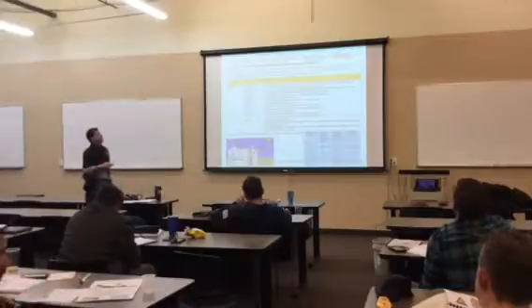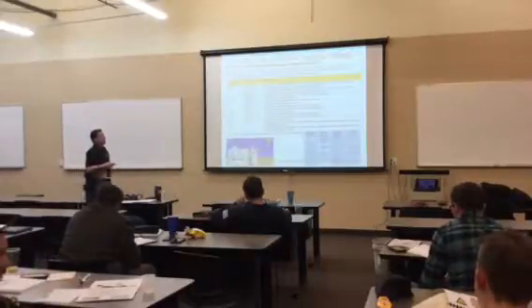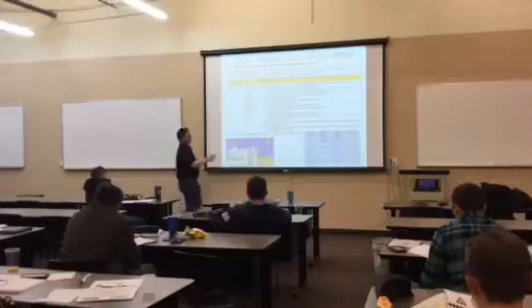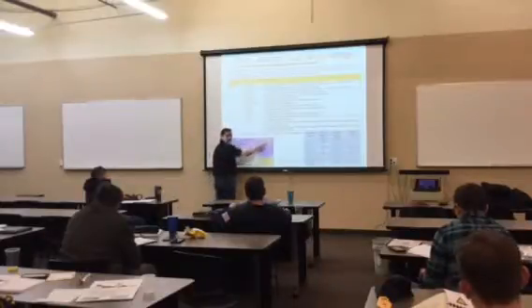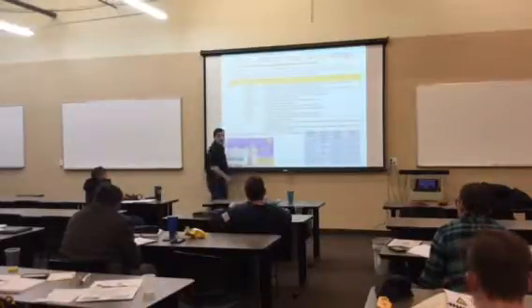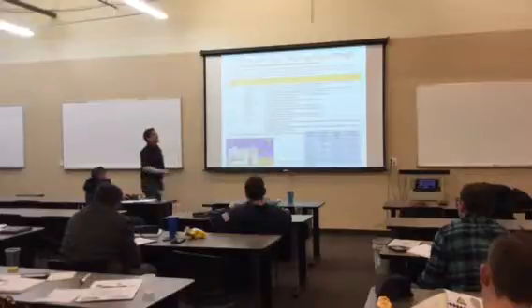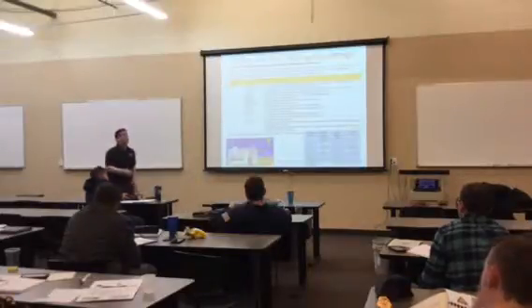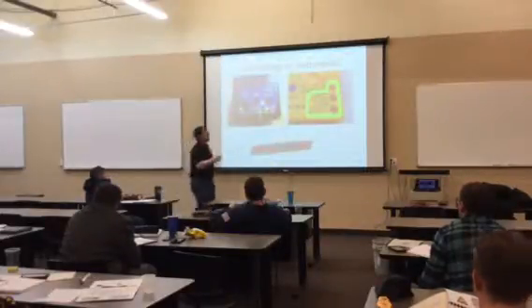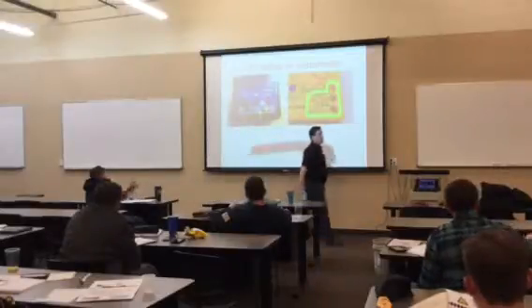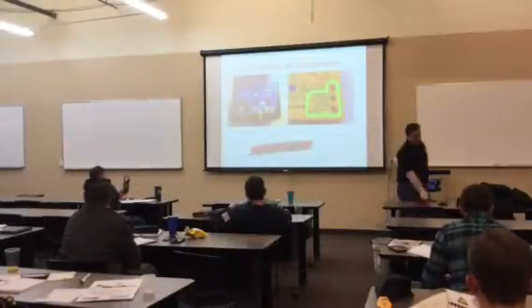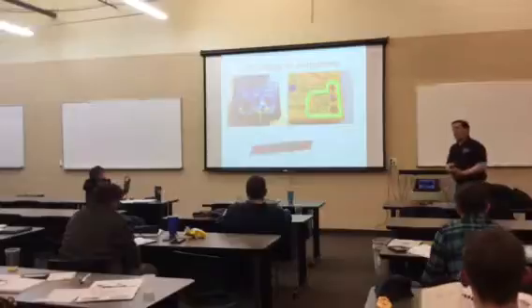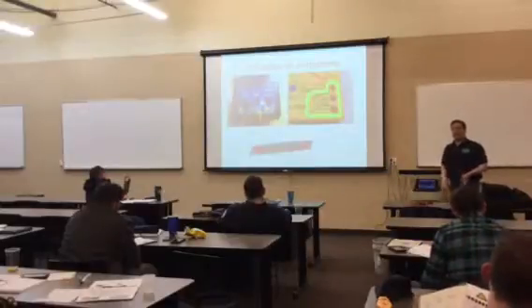Category 4, this is the 3-phase utility connection in any outdoor conductor. That means between here and here, which we're not going to be working on. Meters are rated for these different categories. And it's going to be listed right on the meter. Look at your meter in this vicinity, usually near the plug, and see what category level you're at. It's going to give you a cat rating plus a voltage rating.